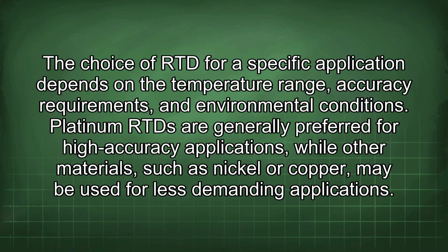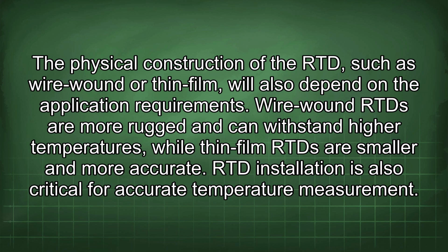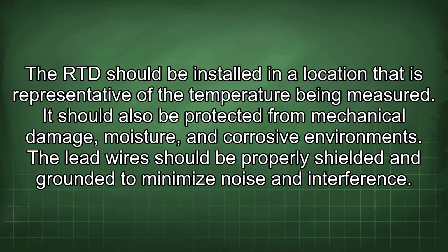The choice of RTD for a specific application depends on the temperature range, accuracy requirements, and environmental conditions. Platinum RTD are generally preferred for high-accuracy applications, while other materials, such as nickel or copper, may be used for less demanding applications. The physical construction of the RTD, such as wire wound or thin film, will also depend on the application requirements. Wire wound RTD are more rugged and can withstand higher temperatures, while thin film RTD are smaller and more accurate. RTD installation is also critical for accurate temperature measurement. The RTD should be installed in a location that is representative of the temperature being measured. It should also be protected from mechanical damage, moisture, and corrosive environments. The lead wires should be properly shielded and grounded to minimize noise and interference.